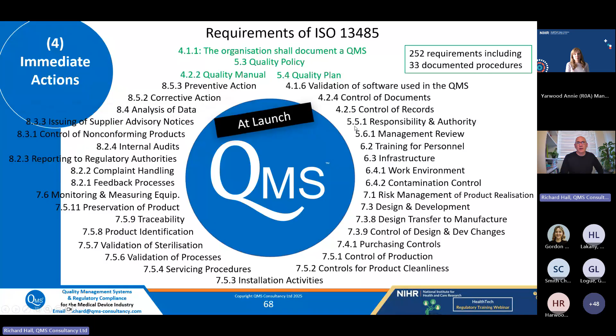And you might be looking at this thinking, okay, we need an actual documented procedure for this. That's a job in itself. That is a quality management system, and that is a job in itself. And it's a requirement of all the regulations. However, this is at launch. So if you're just starting off and you've got the basic products, there's only a handful of documents which you need and should be having within your quality management system. So traceability, things like lot numbers and part numbers of materials you use and things you create, very important.